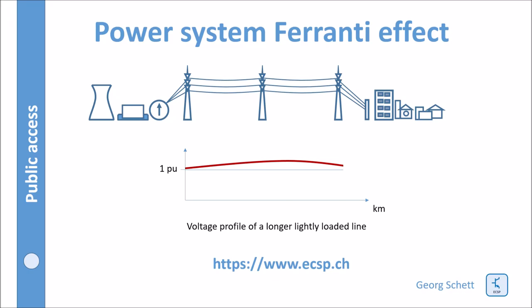In this tutorial, let's talk about the Ferranti effect. The Ferranti effect is a voltage increase along a power line at low load conditions. It starts to be significant at line lengths well above 100 kilometers and can reach well above 50 percent on very long lines. Countermeasures have to be taken to avoid damage to equipment such as transformers, breakers, or other devices.